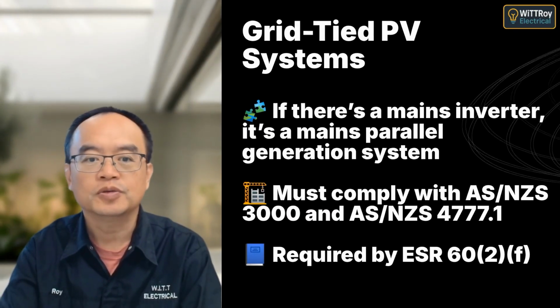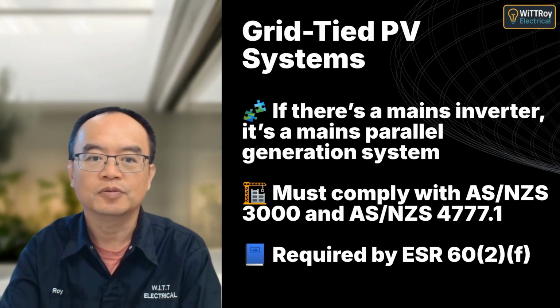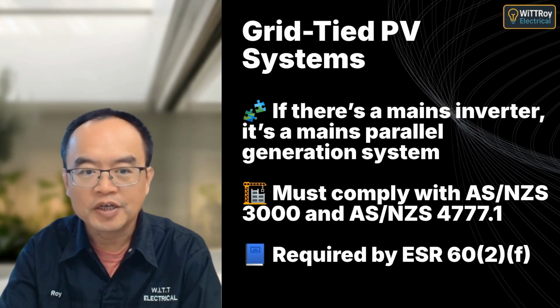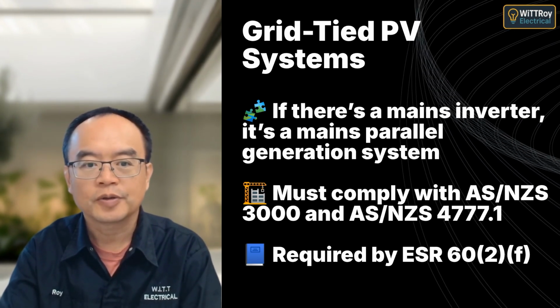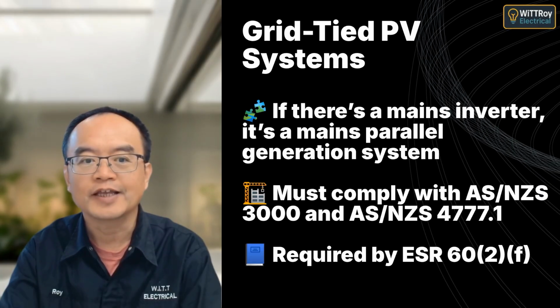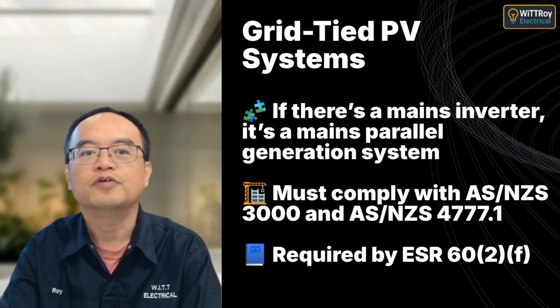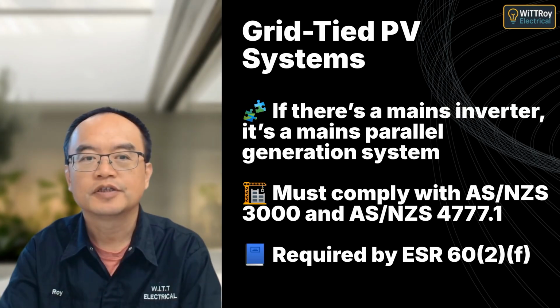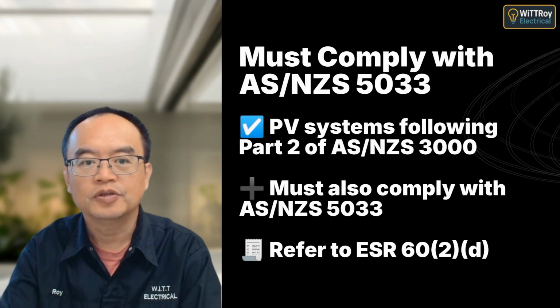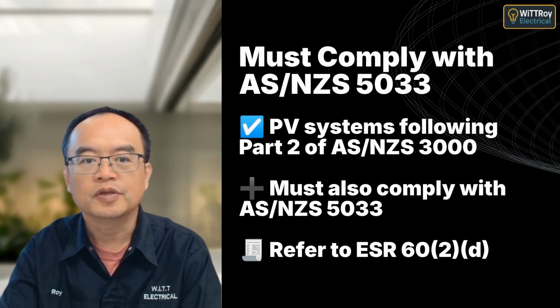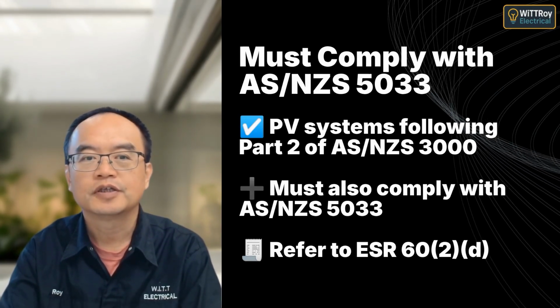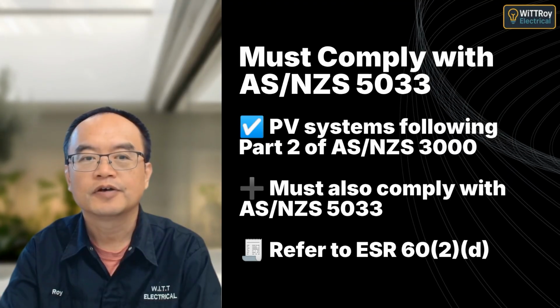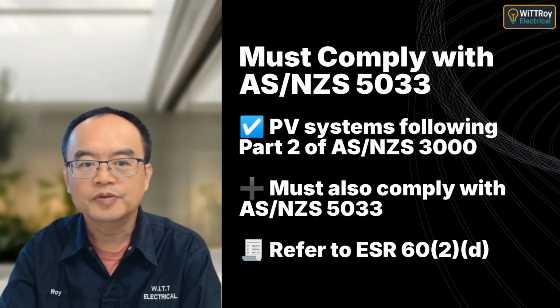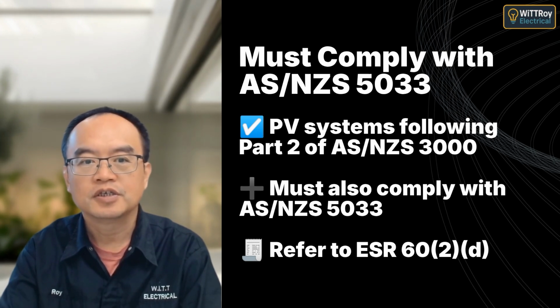When your PV system includes an inverter that connects to the national grid, it becomes a mains parallel generation system. Under ESR 60(2)(f), it must comply with AS/NZS 3000 and AS/NZS 4777.1, which includes detailed safety and design requirements. ESR 60(2)(d) says that when you install a photovoltaic system under Part 2 of AS/NZS 3000, it must also comply with AS/NZS 5033. This standard covers specific PV safety and installation conditions such as string configurations, labeling, and disconnection devices.